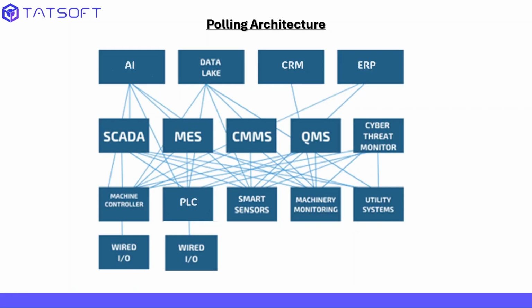This shows the pyramid as individual software and controllers. As you can see, it is very complicated. Every software that wants data must have a connection to the source of the data, possess the correct driver to communicate, and request the data at a specific interval, typically every second, which is why we call it a polling architecture. For large applications with thousands of values, the amount of network traffic can become a problem. Also, it is not very scalable.